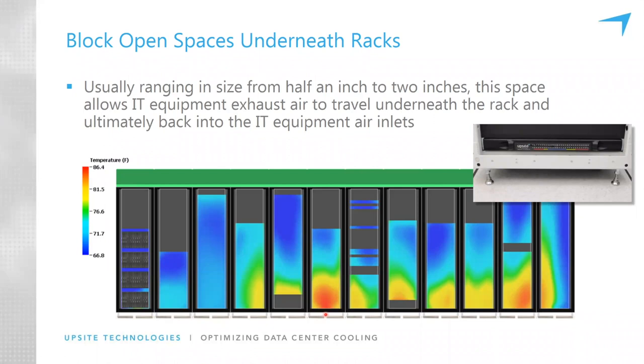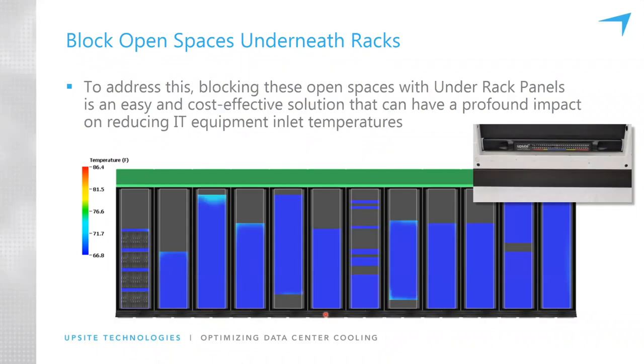So this is the way it should look. And this is what the CFD analysis shows when that space underneath the cabinets is sealed. This is a photograph of that space underneath the cabinet being sealed by an under rack panel, just blocking off that space, just preventing that opening from being a path for air to flow from the hot aisle back into the cold aisle.